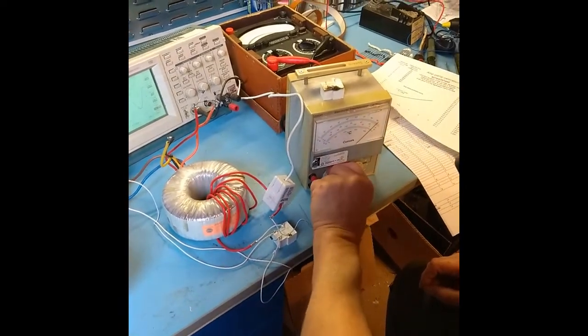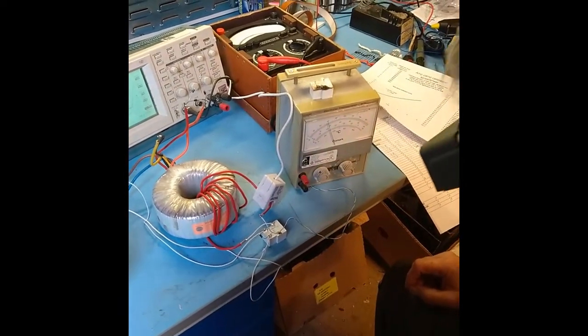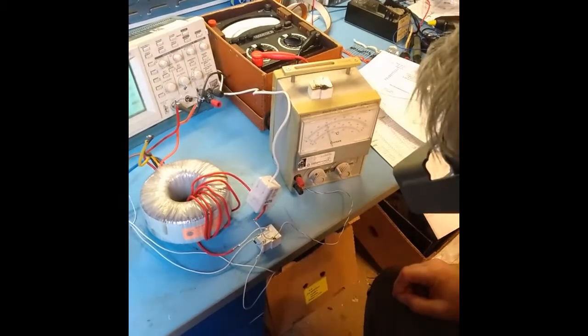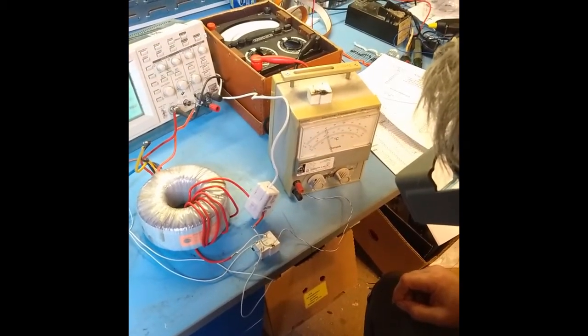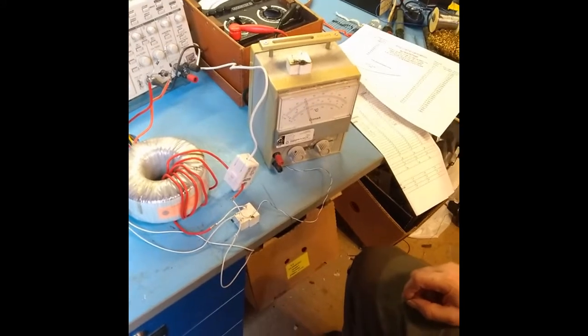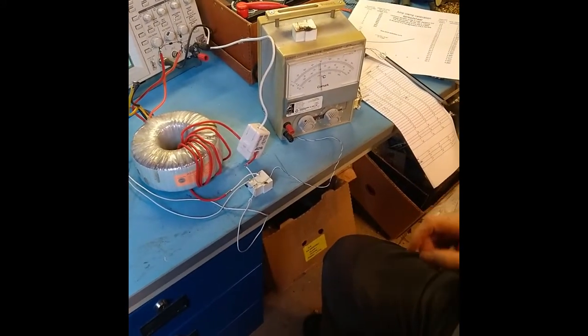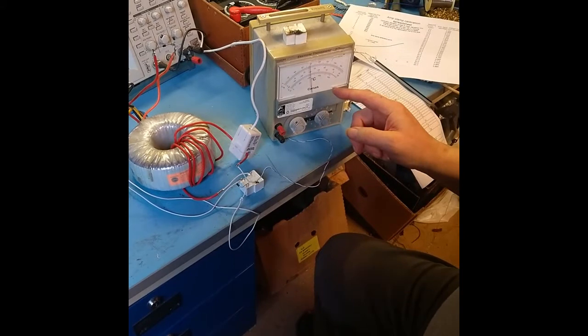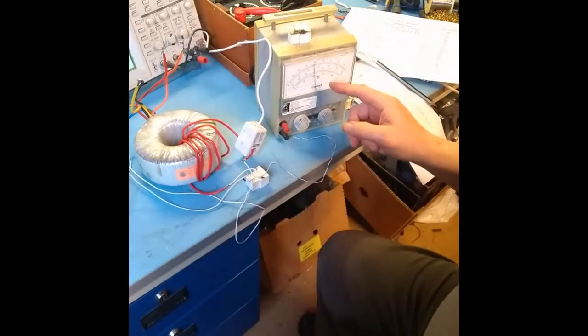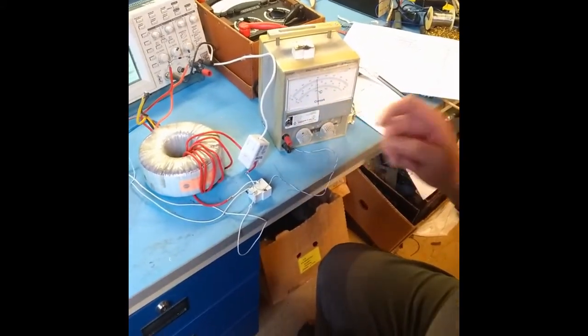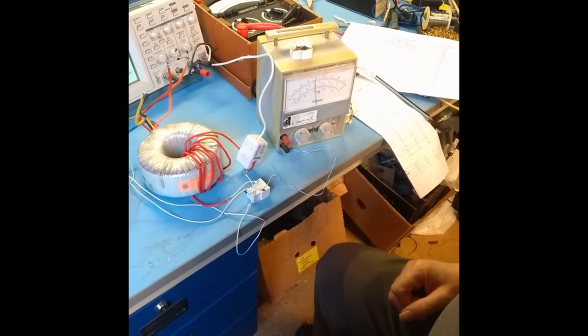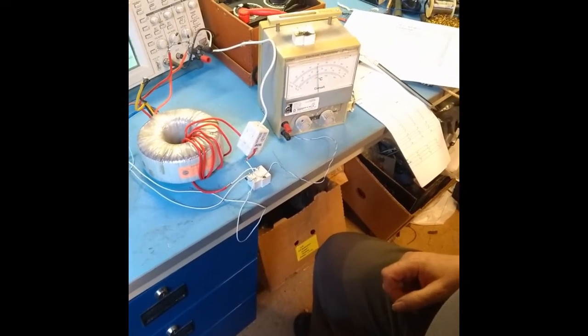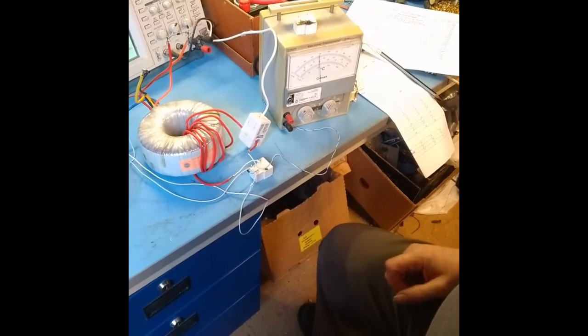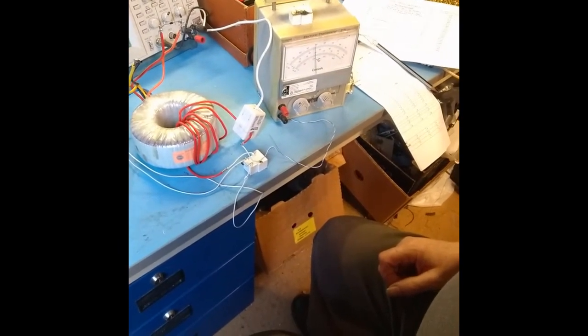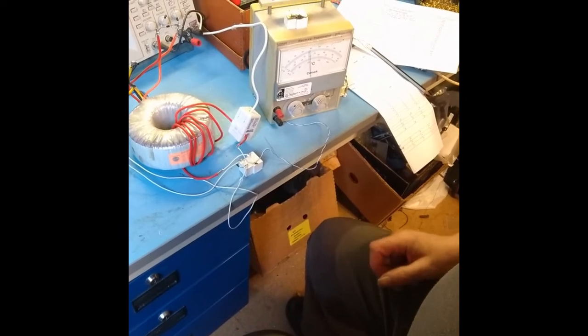I'm going to have to change the scale onto the C scale. And I'm going to give it time to stabilize. We're at 76 degrees now on the temperature meter, and that is at 20 amps. To be honest, I'm surprised it's not higher. But this is the measurement.